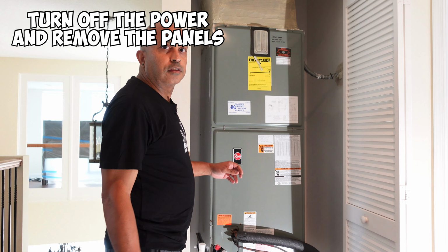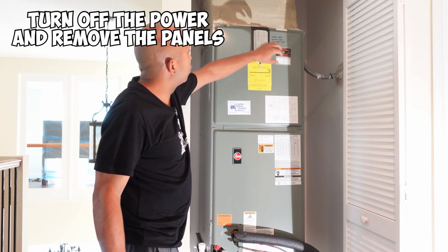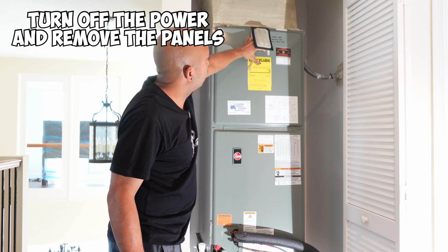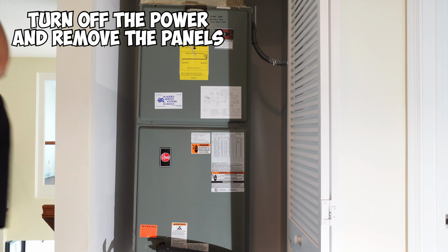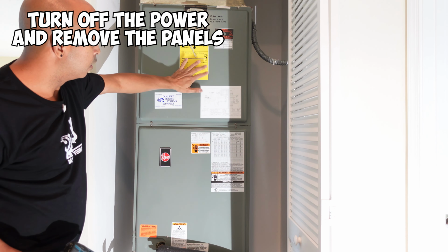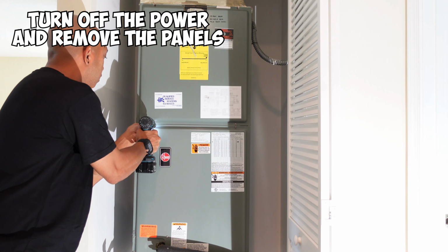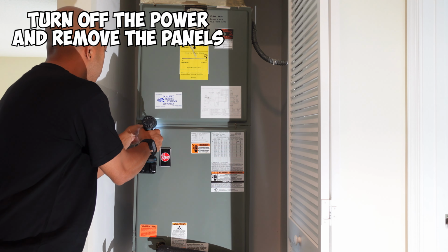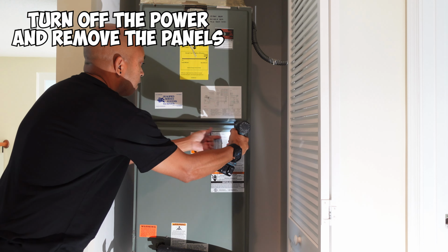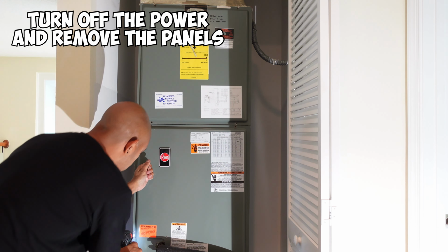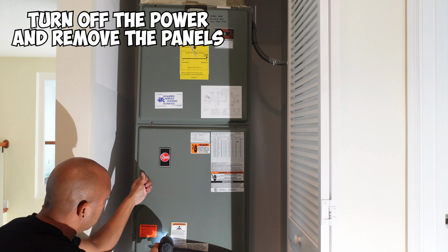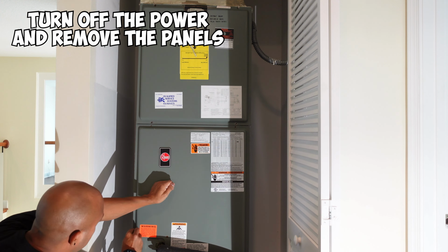The next thing we want to do is turn off the breaker to our AC. This is either on the front of your AC unit or at your breaker panel. Once you guys have the breaker turned off, we're going to want to remove all the panels on the front of our AC, and these are just held in place by a bunch of screws located all around your AC panel. Usually it's a 5/16 or a 1/4 inch socket that you need.